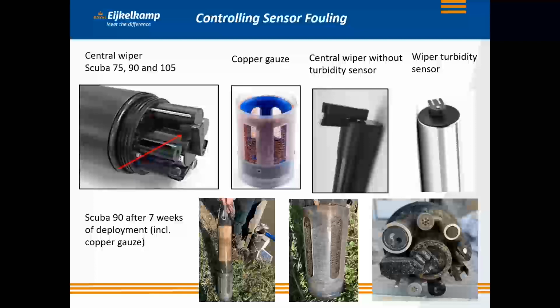For controlling sensor fouling we have several options: a central wiper, copper gauze, and a special wiper on the turbidity sensor. The central wiper is a hairy one, only available for the Scuba 75, 90, and 105. The copper gauze can be placed on any sensor. The central wiper without a turbidity sensor can be used if you want to remove the turbidity sensor and instead put a wiper for all the sensors in the outer circle of the probe. If you only want a turbidity sensor, for instance in a 3-meter setup, there's an integrated wiper on the turbidity sensor.